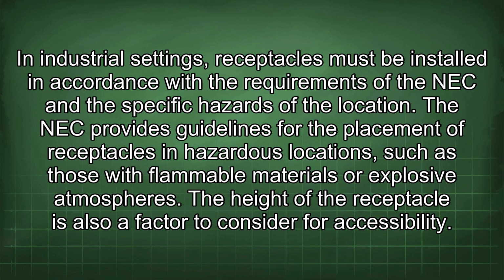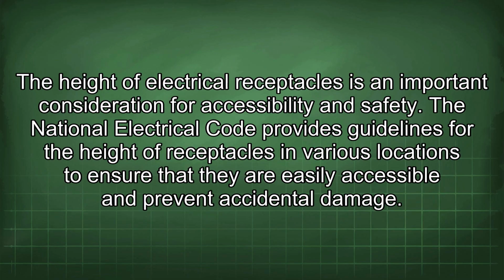The NEC provides guidelines for the placement of receptacles in hazardous locations, such as those with flammable materials or explosive atmospheres. The height of the receptacle is also a factor to consider for accessibility. The height of electrical receptacles is an important consideration for accessibility and safety. The National Electrical Code provides guidelines for the height of receptacles in various locations to ensure that they are easily accessible and prevent accidental damage.